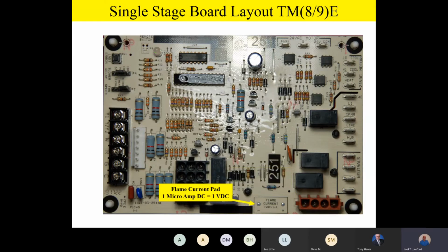Now this is a feature that I really like about our Champion furnaces as well. All of our Champion furnaces feature a flame current pad. What this does is allow you to take a regular voltmeter, put it on DC volts, and go between those two little solder terminals there with your leads, and you can read flame current with the furnace running, with your voltmeter.